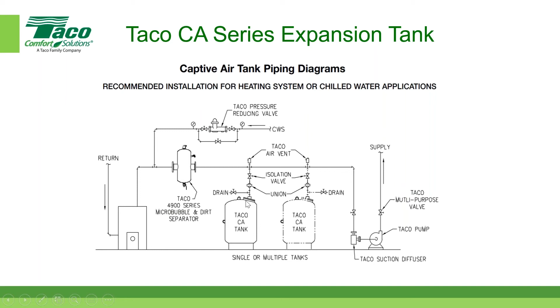So really, that's pretty straightforward, but that is the valving I was talking about, with an air vent on top. Here's another style expansion tank, and this is our CBX model. This is a partial acceptance, okay? And this bladder looks a little different than that picture I showed you earlier. So this is actually mounted from below. The water still goes on the inside of it, so the system connection is at the bottom. But this is a partial acceptance, and I think most of us, just by visibly looking, can see that bladder would not expand to fill up the whole tank.